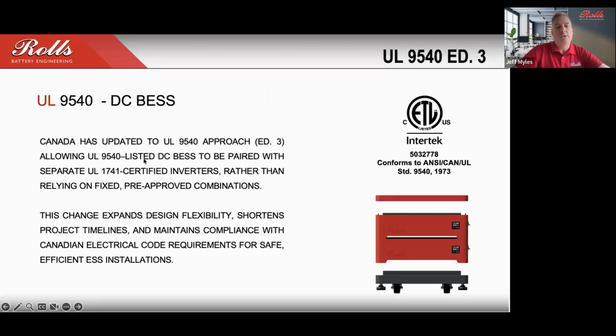So the first thing that I wanted to go through was essentially talking about the UL certification on this product. When this product was tested, it was tested to UL 9540 Edition 3, which is a DC ESS pathway. What that means is this product is not tied to a specific inverter for pairing as far as residential application. And so that restriction is no longer required, which you would see in Edition 1 and Edition 2. This allows a lot more flexibility with connecting to other inverters.